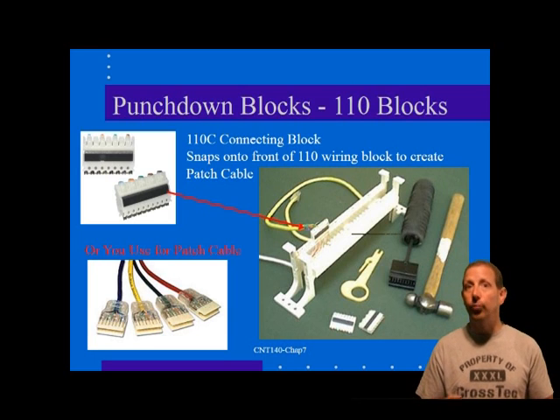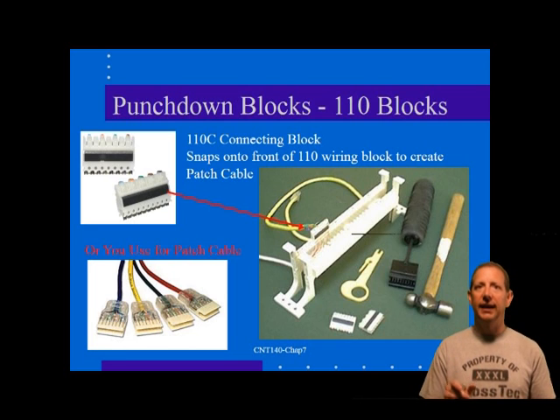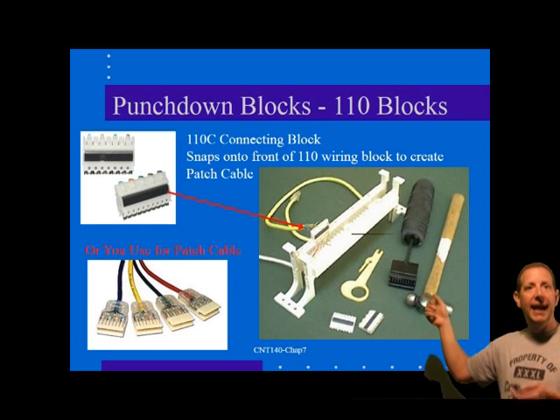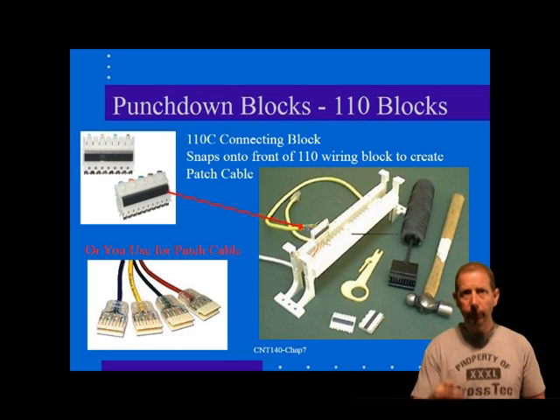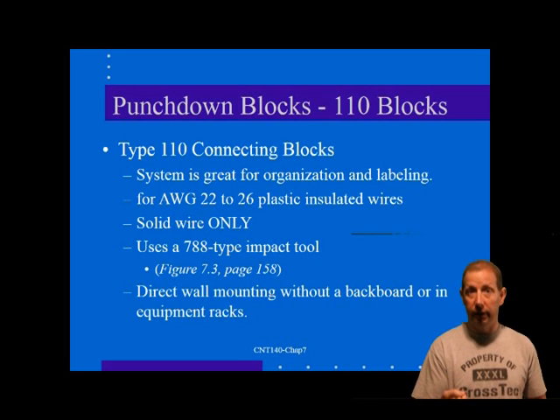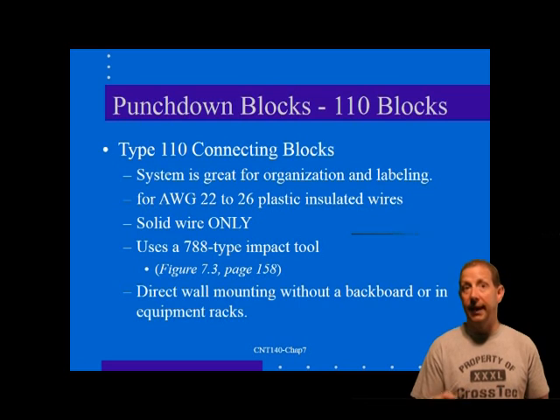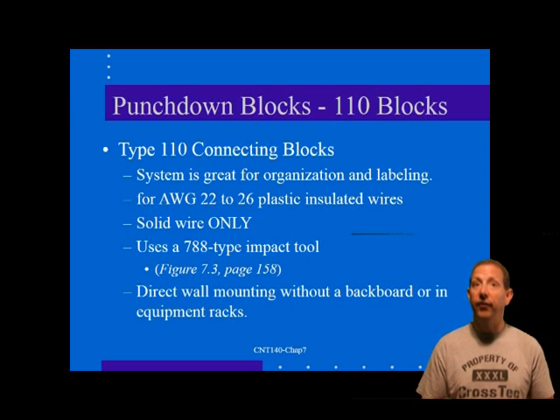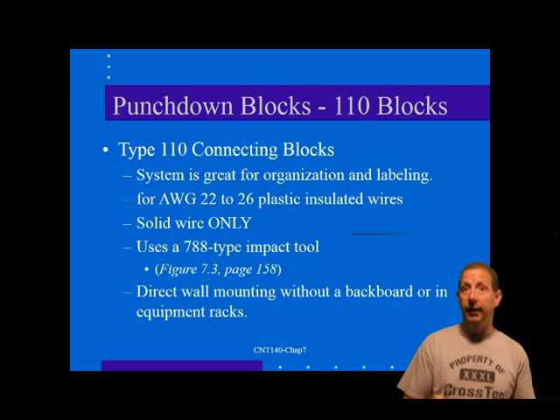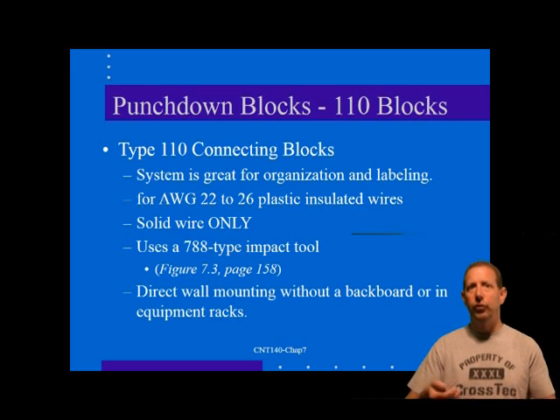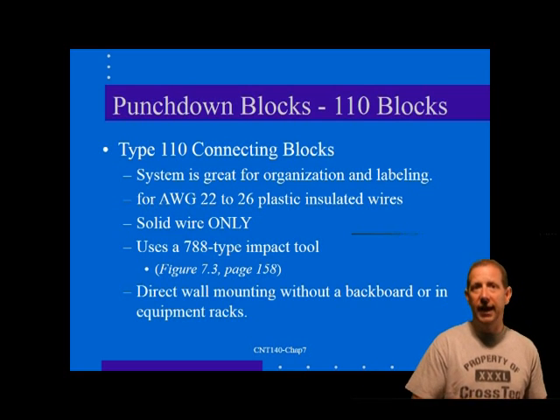Once the incoming cable wires are routed into the wiring block, they are electrically terminated by the insertion of a 110C connecting block. The 110C connecting block is a small wafer-like plastic housing containing metal contact clips at opposite edges. The blocks are designed to snap onto the wiring block strips and connect to the wires held in place. The back edge of the wafer contains quick clip IDC prongs that resemble the straight portion of one of the 66 block clips. When the connecting block is pressed into place, the wires positioned on the wiring block are then terminated in mass. Each connecting block can terminate from three to five pair, six to ten wires, depending upon the size of the block. The front edge of the 110C connecting block is used to terminate cross-connect wires, or occasionally other cables and adapters.